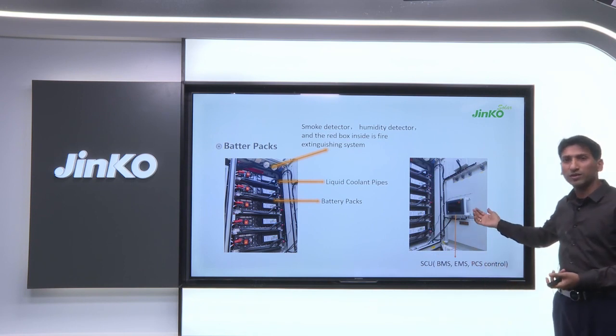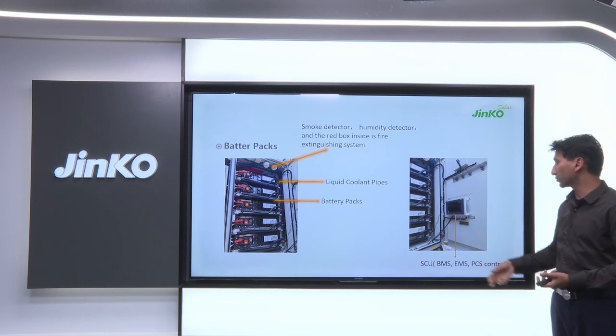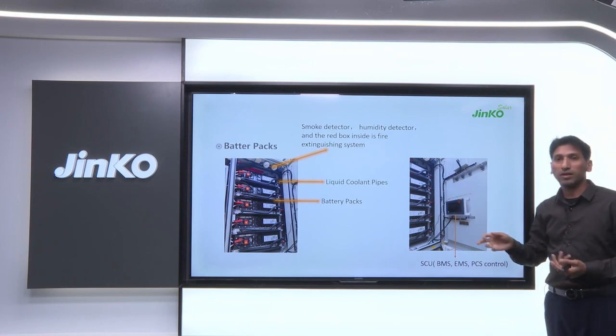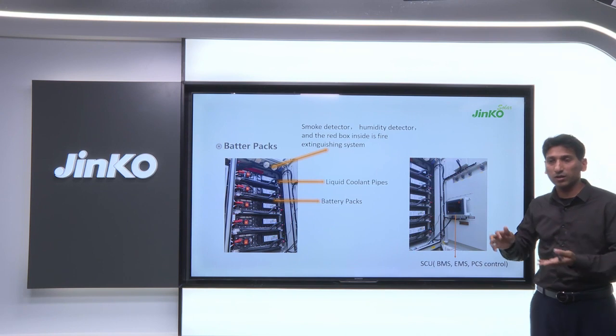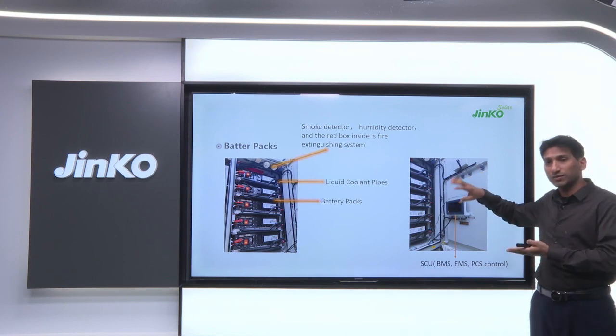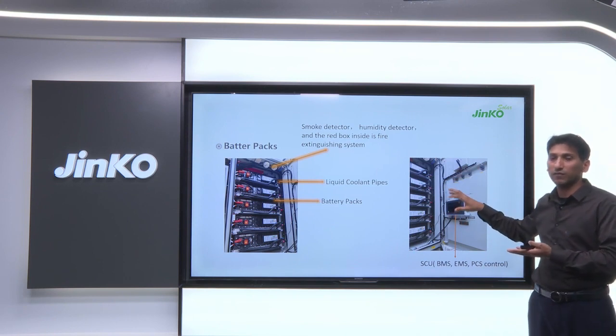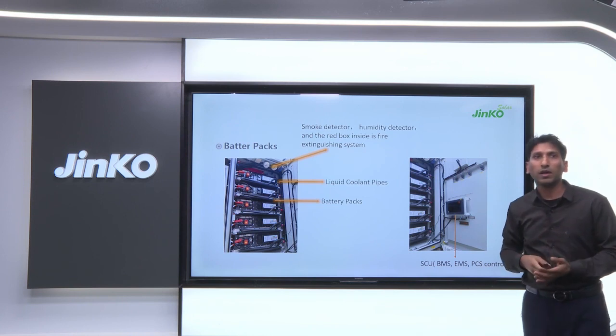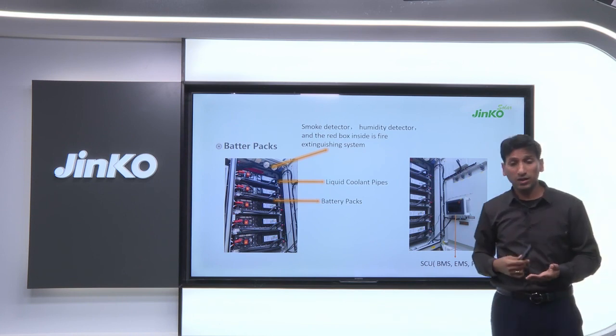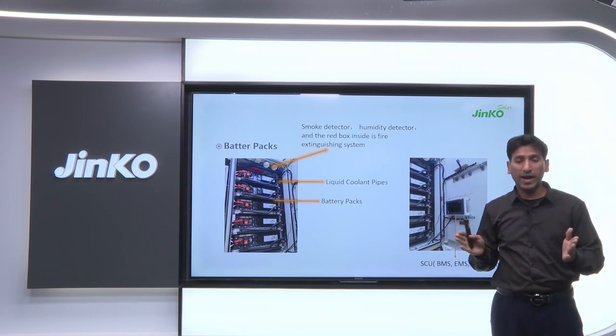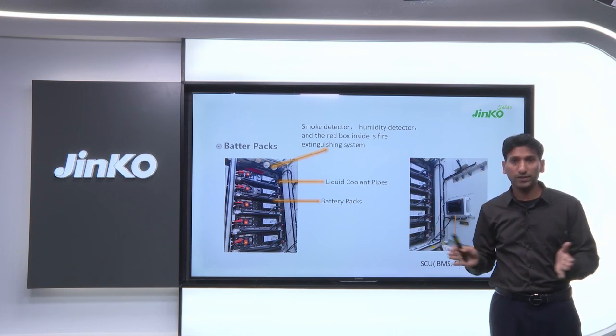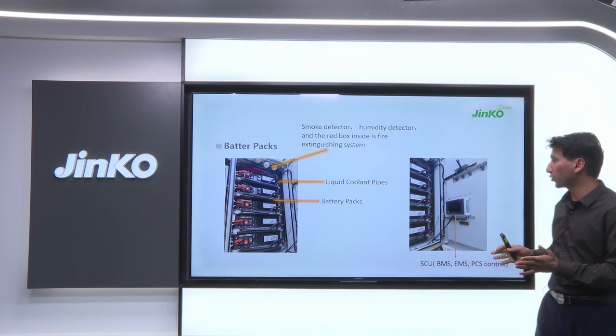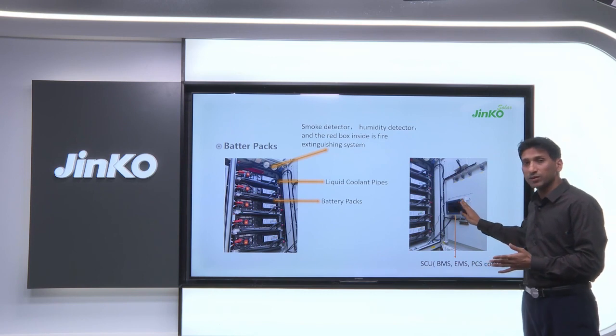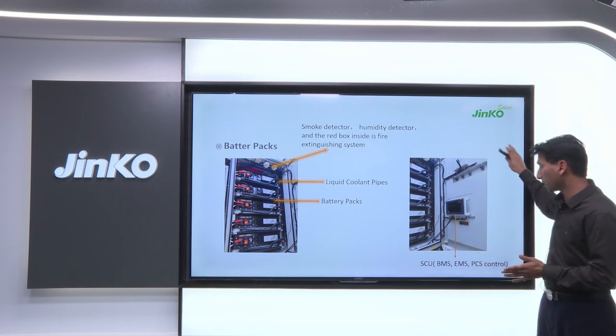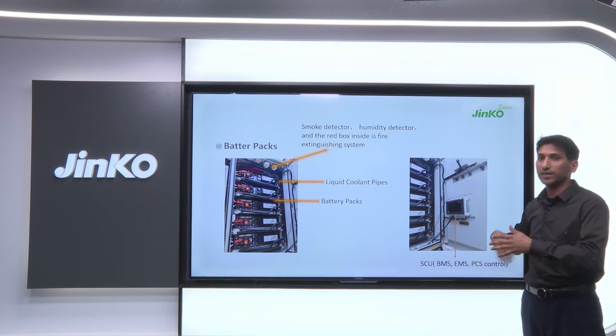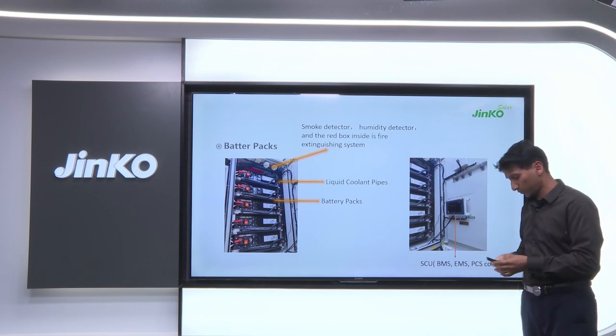But you can only see this in the master cabinet, because the master cabinet is used to connect and control all the other slave units that we connect together. One thing I need to tell you is we can install 9 Sun Giga units together. All these 9 Sun Giga units don't have any SCU, only the master cabinet has one, and they are all connected here in this unit, which can control all of them together.